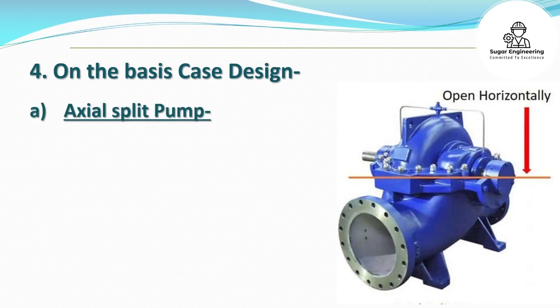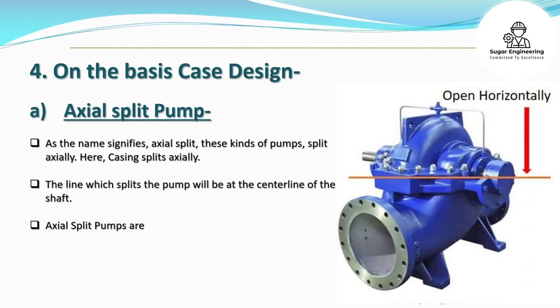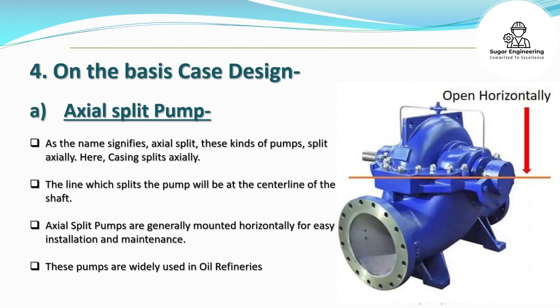On the basis of case design: A. Axial split pump. As the name signifies, these kinds of pumps split axially — the casing splits axially. The line which splits the pump is at the centerline of the shaft. Axial split pumps are generally mounted horizontally for easy installation and maintenance, and are widely used in oil refineries.